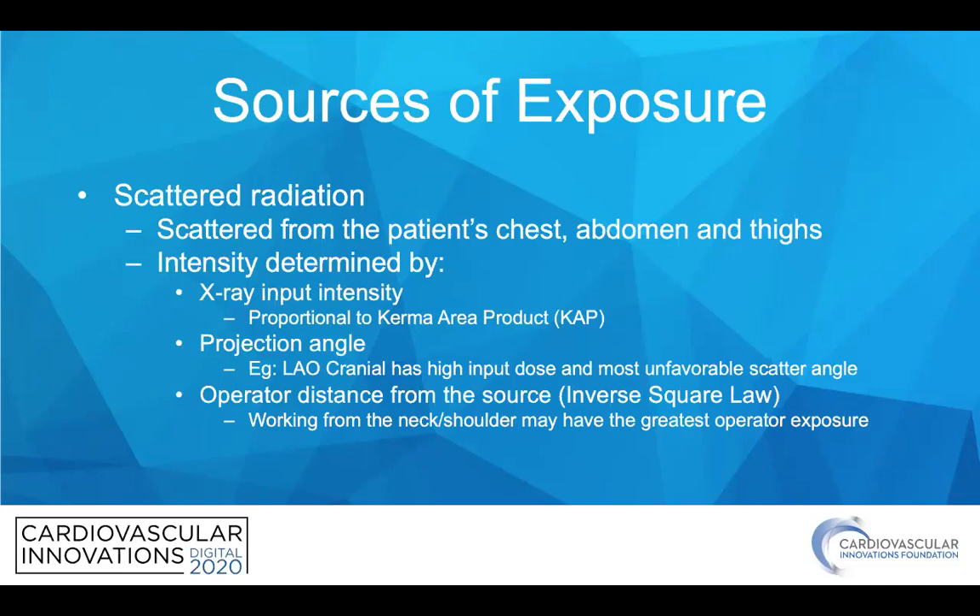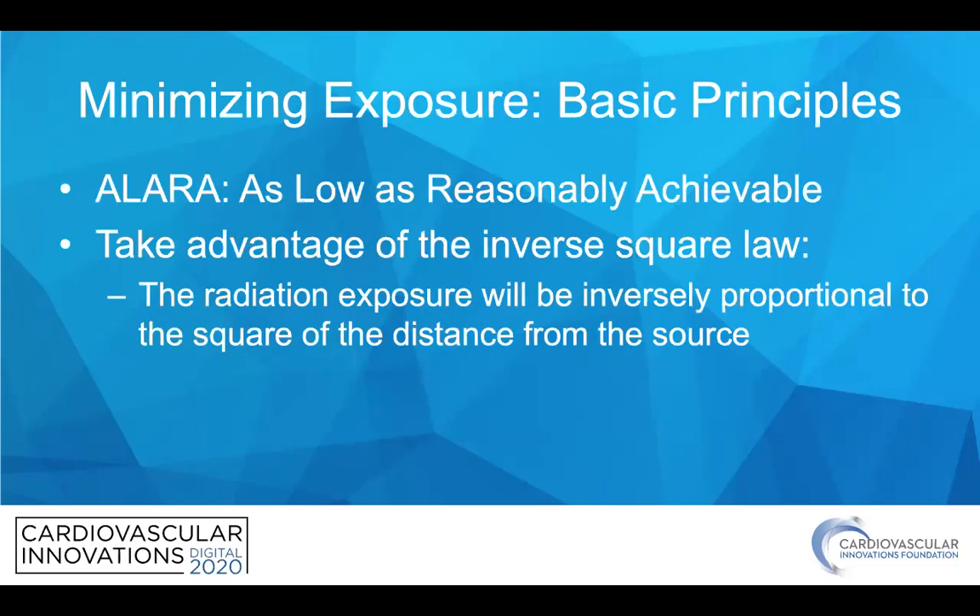The projection angle also matters, with certain angles being substantially higher in dose, such as the LAO Cranial view, and the operator distance from the source is important. To minimize exposure, we follow the ALARA principle — as low as reasonably achievable radiation dose — and we take advantage of the inverse square law, with radiation exposure being inversely proportional to the square of the distance from the source.